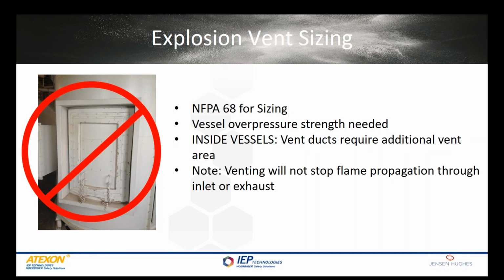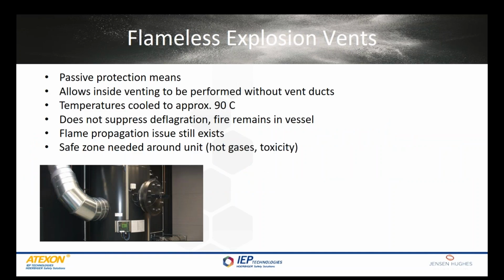Another thing to keep in mind, explosion vents relieve pressure from the primary vessel. Explosion vents do not stop flame propagation from that vessel to interconnected vessels through ducts, pipes, chutes, and so forth. We'll cover that in a few minutes. In some instances, a different type of explosion vent can be used for inside applications where vent ducting is not practical, cannot be done safely to the outside, or the vent duct length is just too long to be suitable for the application. That would be the use of flameless vents.